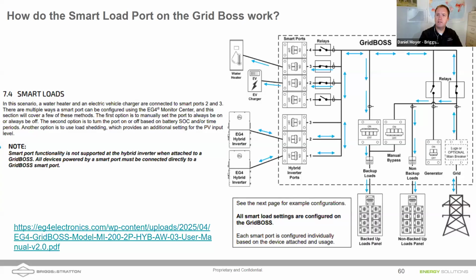Let's talk about those smart loads inside the Grid Boss a little bit more. This is a great feature for a couple of reasons. One, when we start to look at some of the NEC code as it relates to sizing these energy storage systems, NEC doesn't specifically say you need a certain amount of kilowatt hours or how many batteries you need in the system. But code is starting to talk a little bit about how large a system needs to be able to power the loads. Some of the older versions said that you only need to be able to power the single largest load in a home. Some of the newer codes, though, are starting to reference that you need to be able to back up an entire home's loads with one of these energy storage systems.